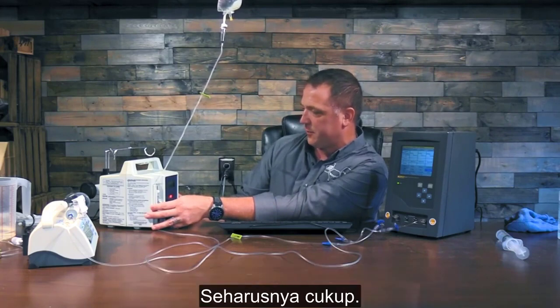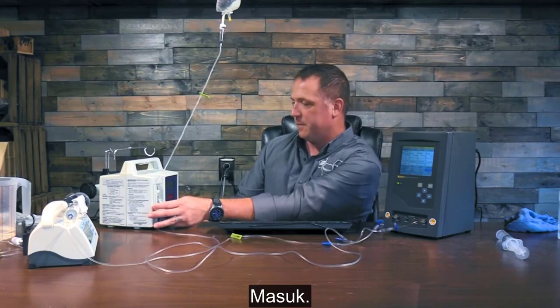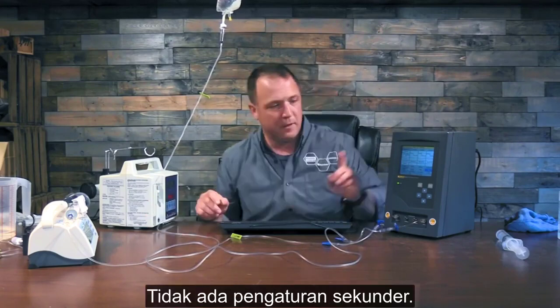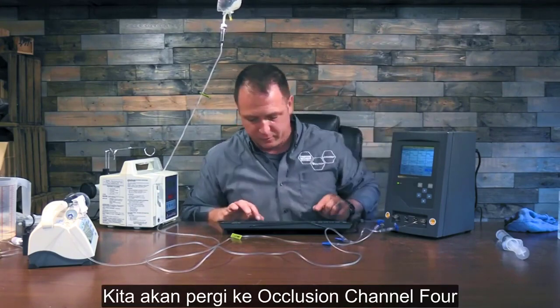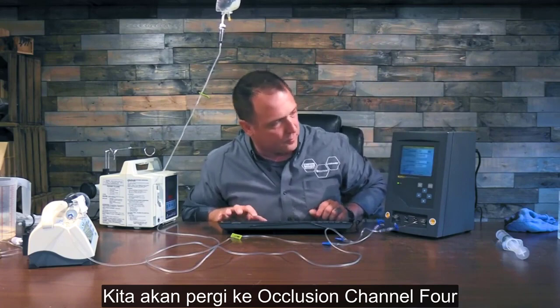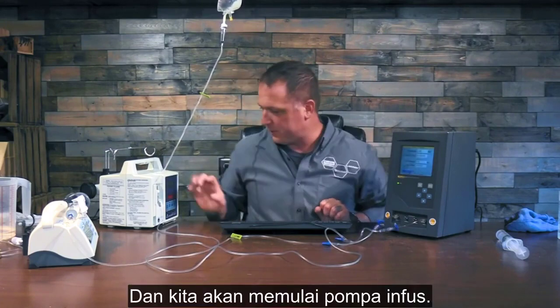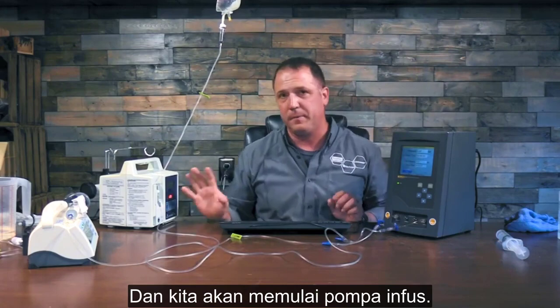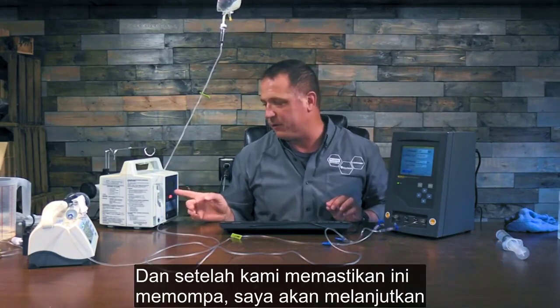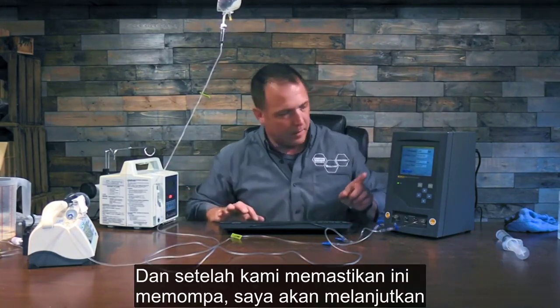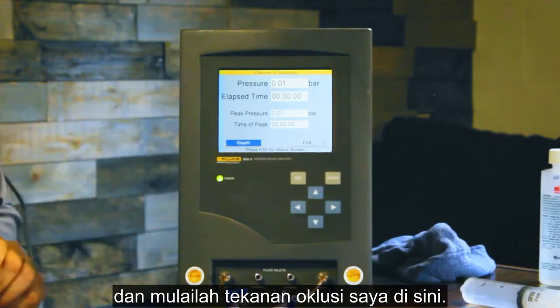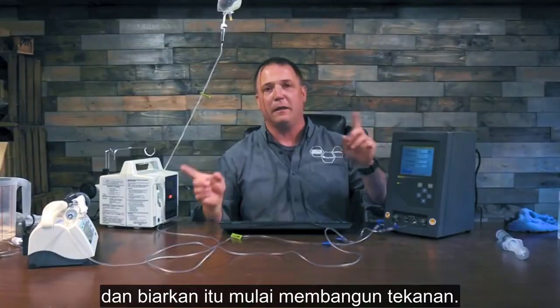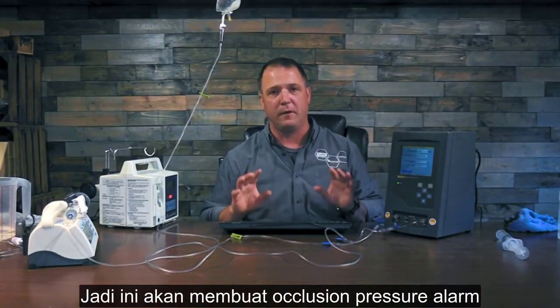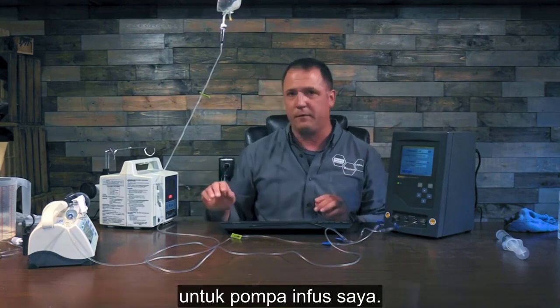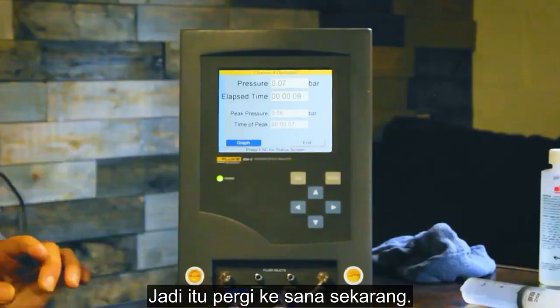We'll put 20. It should be ample. Enter. No secondary setting. And on our infusion pump, we're going to go to occlusion, channel 4, and we're going to start the infusion pump. Once I make sure this is pumping, I'm going to start my occlusion pressure over here. It's going to shut the valve and let it start building pressure. So this will find our occlusion pressure alarm for my infusion pump. So that's going there now.